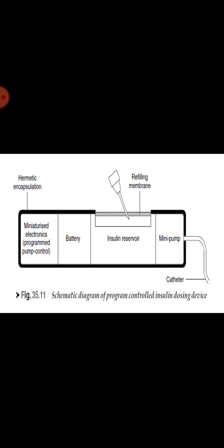All infusion routes should be possible and practicable, including intravenous, peritoneal and intramuscular. The pump must have sufficient supply pressure in reserve to prevent possible catheter clogging through microthrombi. And the highest possible level of patient safety must be assured. Malfunction of the device must be excluded as far as possible or must be signaled immediately to the patient and must never lead to dangerous overdosing.